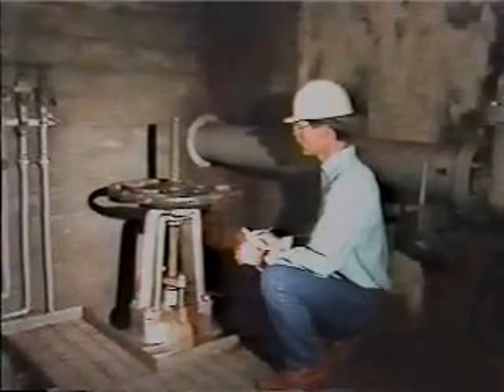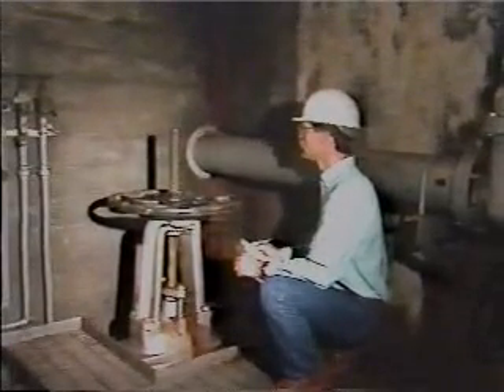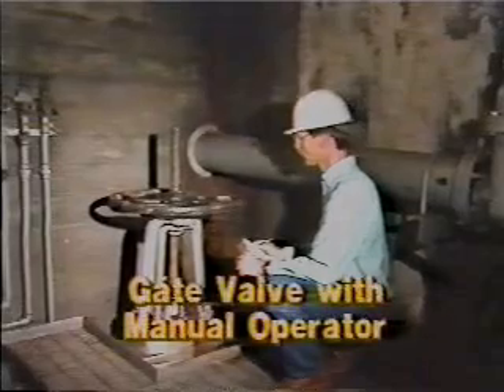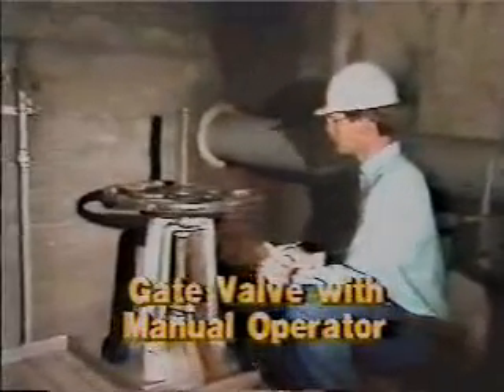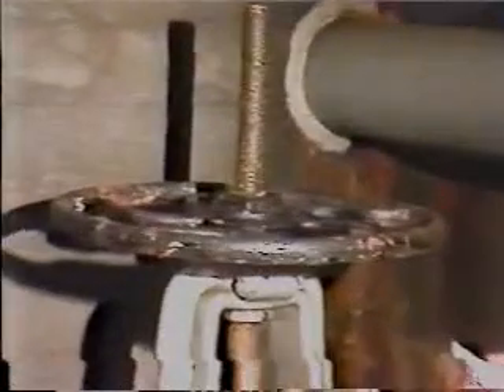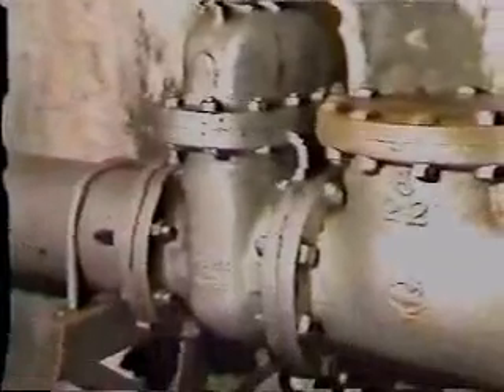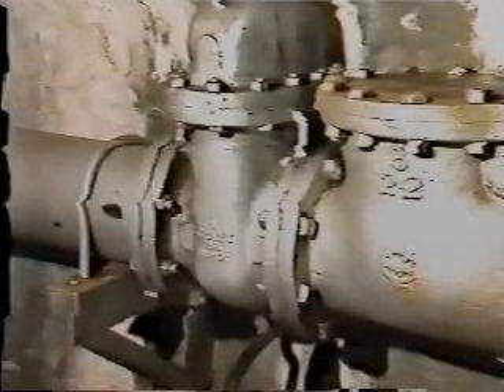Now let's look at inspecting valves. The first example is a gate valve with a manual operator located in a small conduit. Although many of the gate and valve problems are the same, valves may sometimes be difficult or impossible to inspect. Some valves are fairly small, and when they are within a conduit that is 30 inches or less in diameter, they are hard to inspect.